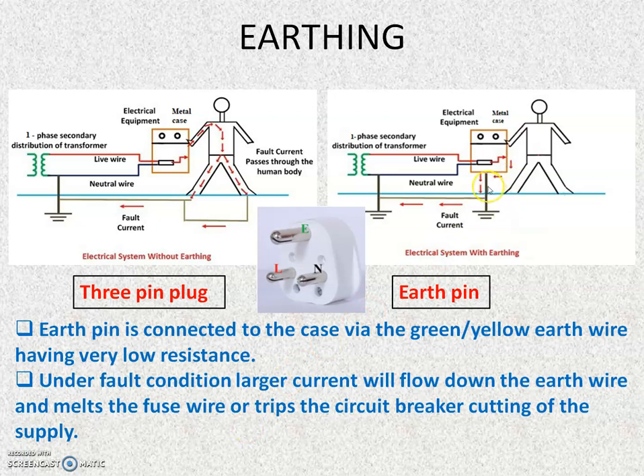One is taking the leakage or faulty current to the ground, thus protecting the user or the operator, and also, in the event of a fault, an earth fault, the current will be very high and it will trip the fuse or the circuit breaker, thus protecting the equipment also. Thus it is mainly done at the equipment or on the equipment. So this is also called equipment earthing.